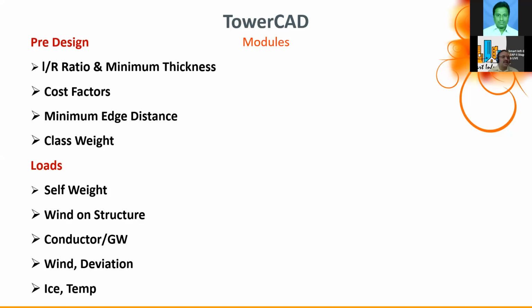The specific code for transmission towers is IS 802. There are different parts for design, load calculation, and so on. The difference between IS 875 and IS 802 is that 802 goes by hourly wind speed. For towers, you take the hourly mean velocity of the wind and apply gust factors. These gust factors are given specific to transmission towers, whereas IS 875 gives factors for general structures, not necessarily towers. That's the difference. We also consider ice and temperature loads.